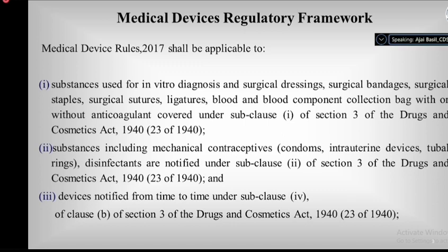When I say Medical Device Rules, the applicability is defined in three different sections concerned with the regulatory framework. The first comes under Section 3B1 of the Drugs and Cosmetics Act of 1940, which includes in vitro diagnostics, surgical dressings, bandages, staples, sutures, and blood component collection bags.